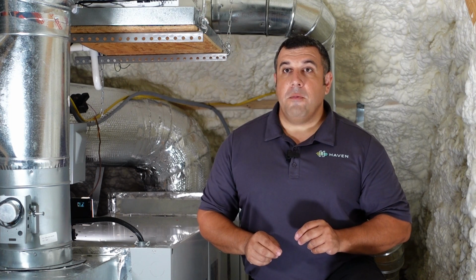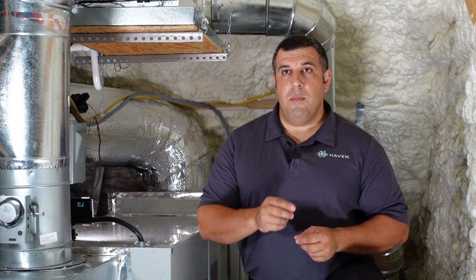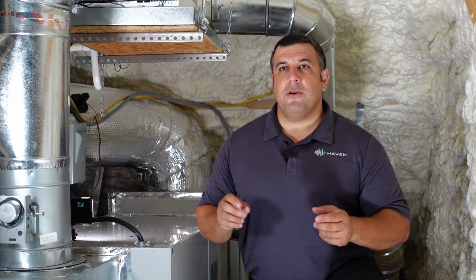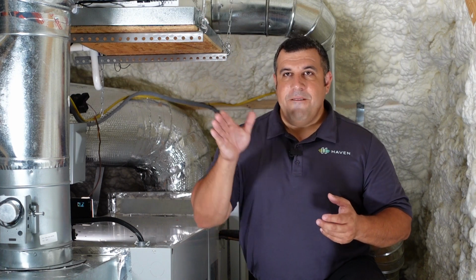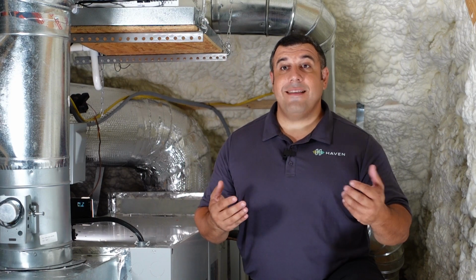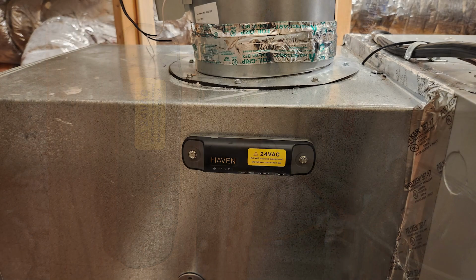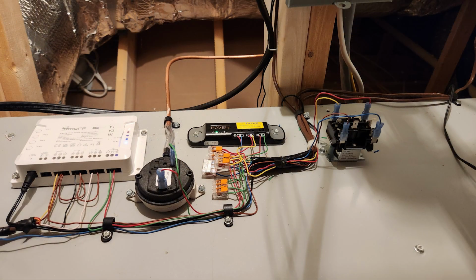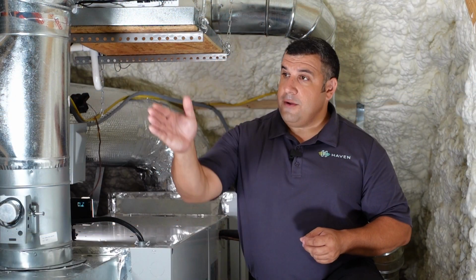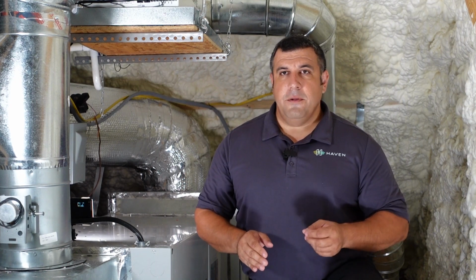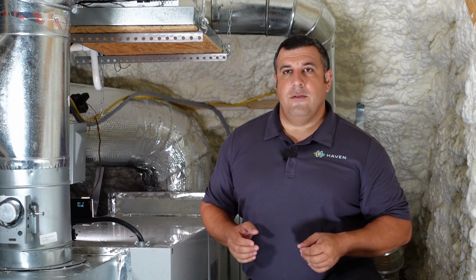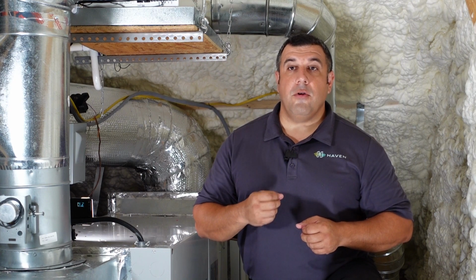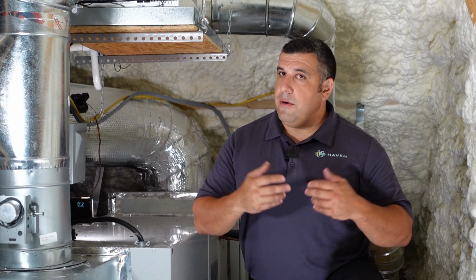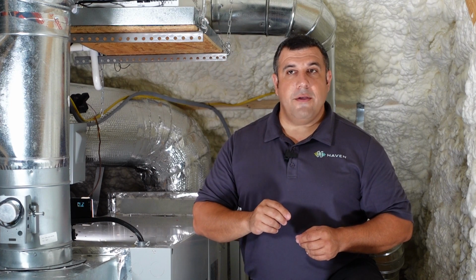The first step is to determine where the Wi-Fi access point is in the home, and place the controller on a metal surface, ideally with no obstructions, facing the access point. This allows a clear path for the controller and the Wi-Fi access point to communicate. Here I'm showing a few options for controller placement in the furnace room in my home. In this house, I know that the access point is approximately over there, so I can put the controller in really any of these locations. Finally, we don't want to install the controller anywhere that it can be easily bumped, or anywhere with a direct obstruction that would block the Wi-Fi signal.